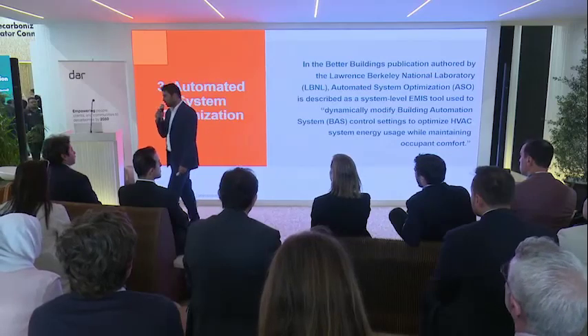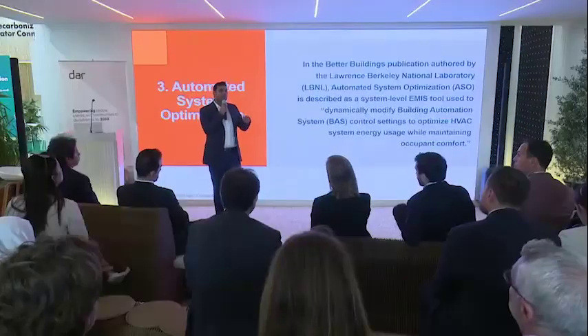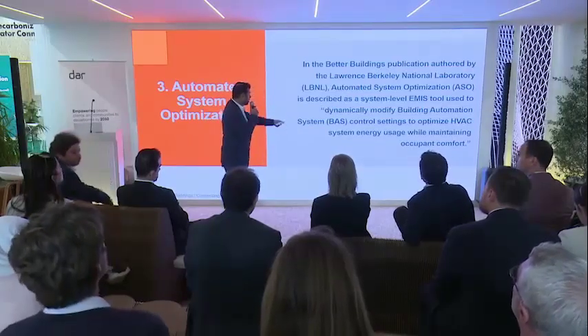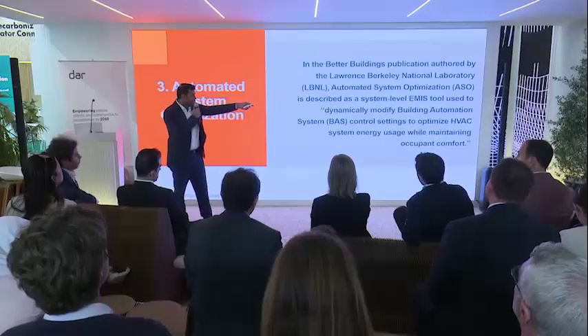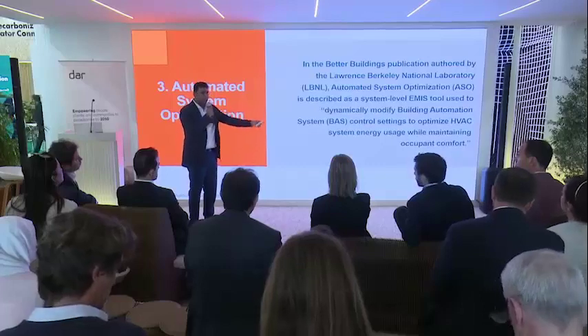Now, let's move on to the third out of the four categories under EMIS. This is automated system optimization. If you remember when I talked about FDD, I said that the distinguishing factor is that it's a one-way interface. With automated system optimization, the system becomes even more intelligent if you subscribe to use this technology, which is it can write back to your building automation system as well. The key word here being, you'll be able to dynamically modify building automation system control settings to optimize energy consumption while maintaining comfort.